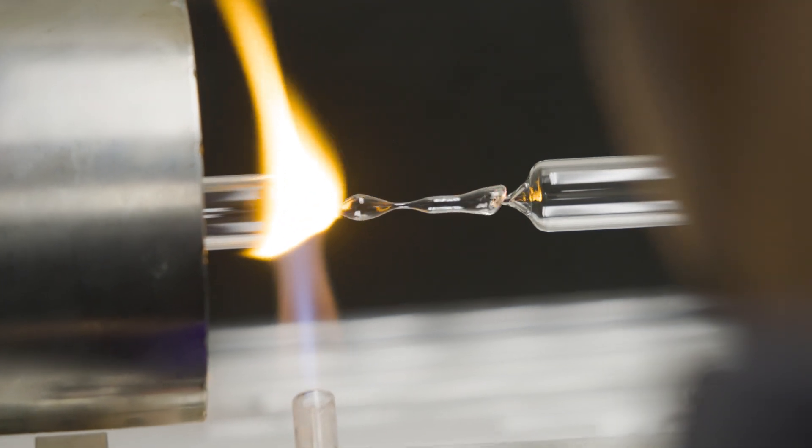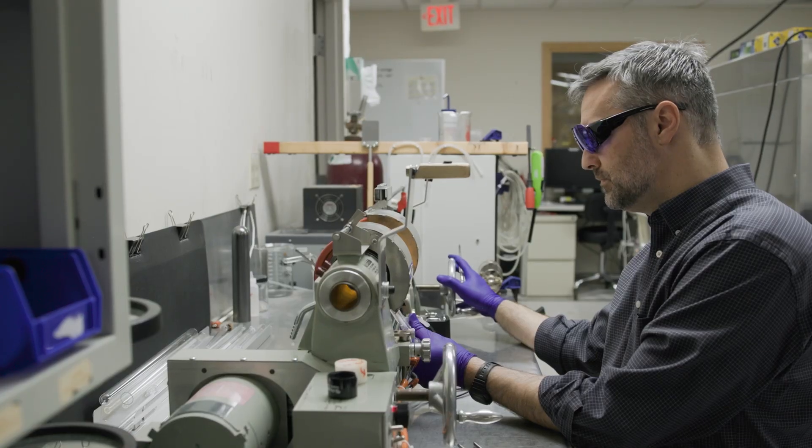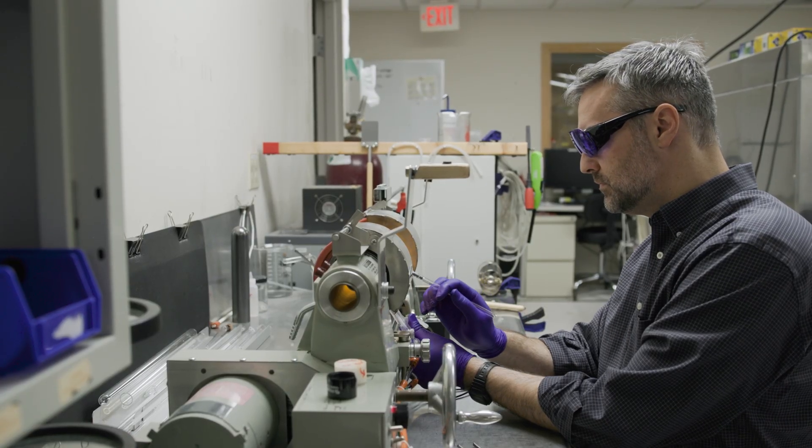And that's a really cool standard. That's like that atomic clock in Colorado. It's a very cool thing that we sell, and it expands out from there. Inside the cell it's a specific temperature and it's always going to be that temperature because it's sealed off. And if you want to verify that something else that you have is also a certain temperature or has a certain amount of ohms in it, you can actually use a triple point of water cell. It's got a baseline, so it's a good way to verify that your equipment is not faulty.